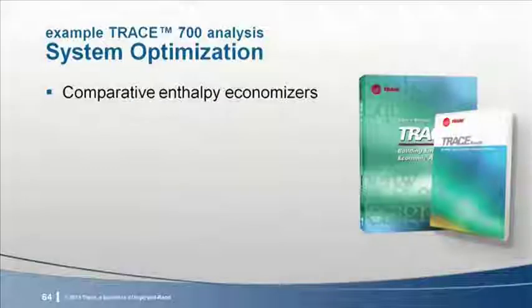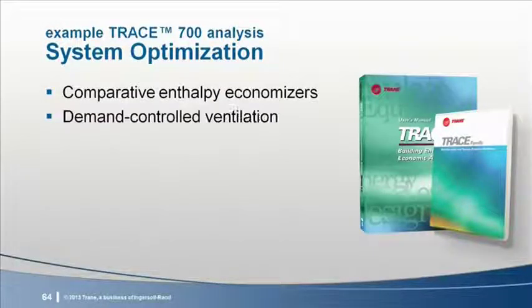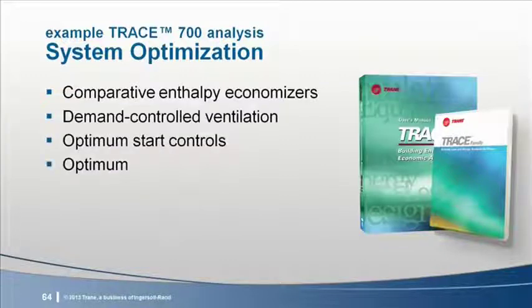Additional energy conservation measures could be added and evaluated to further reduce energy consumption. Comparative enthalpy economizers can be used. Demand control ventilation could be used and in some instances may be required by code. Optimum start and stop controls could be added to enhance comfort and energy usage. These simulations assumed minimally compliant rooftop equipment. That is, the equipment used standard 90.1 efficiency rates.